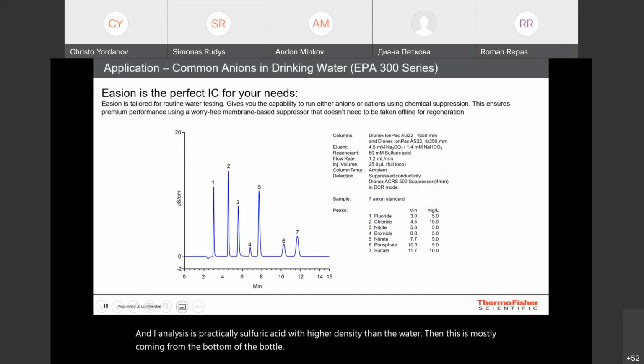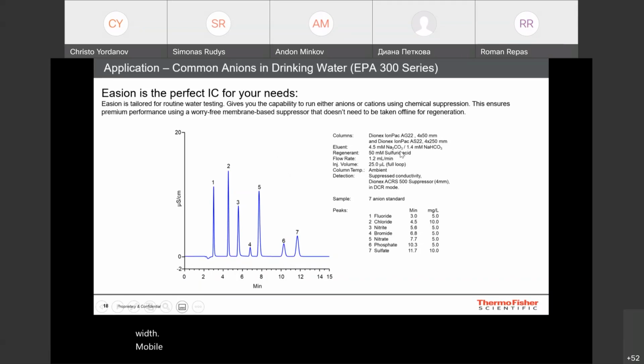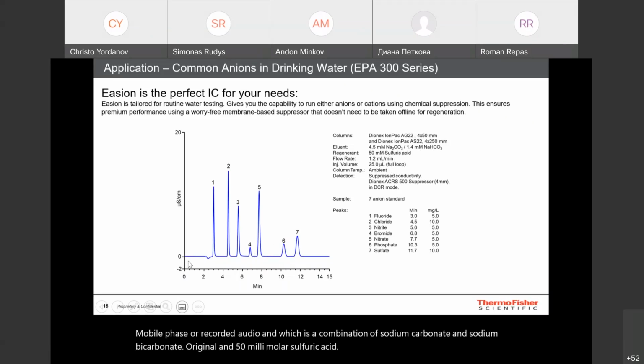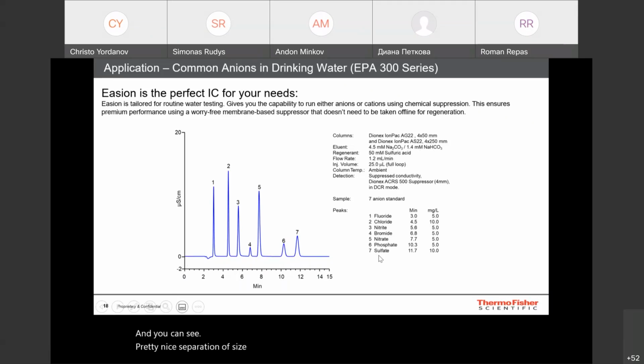Applications. Easion is the perfect ion chromatography system for your needs, if you are looking for a routine testing of easy sample matrices like the water analysis is. So on this slide, you can see the isocratic separation, IonPac AG and AS22 guard and analytical column with mobile phase, or we call it eluent, which is a combination of sodium carbonate and sodium bicarbonate, regenerant at 50 millimolar sulfuric acid. And you can see pretty nice separation of 7 standard inorganic anions in something like 13 minutes.